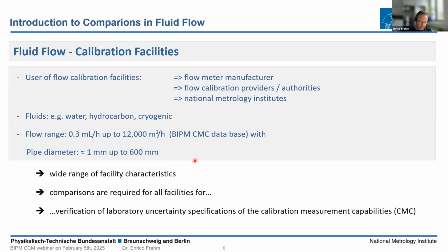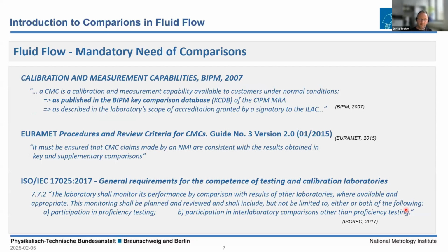But all facilities are required to take part in a comparison or in proficiency testing. The aim of this is to verify their laboratory uncertainty specifications and the calibration measurement capabilities, also called CMC values. The need for such a comparison is regulated in several standards and guidelines. Some examples are given here, like at BIPM, the EURAMET Guide, or the 17025 standard. I don't want to go into detail on that, but for all comparisons it is essential to use a correct and valid evaluation procedure.